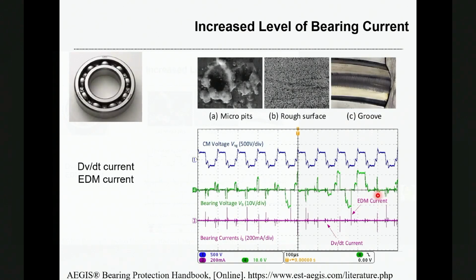So another effect due to high-speed switching is the motor bearing degradation. As an indication, people normally use the bearing current to indicate how the fast switching will degrade the motor bearings. For smaller machines, there are two types of bearing current: the EDM type of current and the dV/dt current. The magnitude of EDM current is much higher than the dV/dt current, and the EDM current will cause more damage.